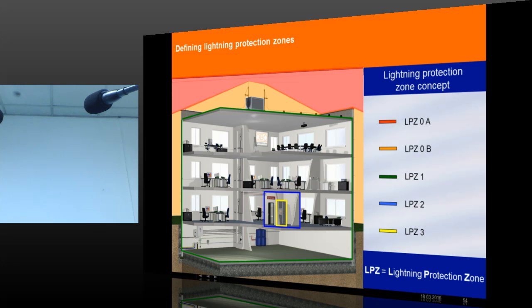Lightning protection zone 0B. LPZ 1 is the assumed outer wall of the building. It is the outer wall of the building. And an inner wall of the building can be assumed as lighting protection zone 2. The metal case of a server, for example, the metal case of a computer, can be assumed as lighting protection zone LPZ 3 or LPZ N, any number.